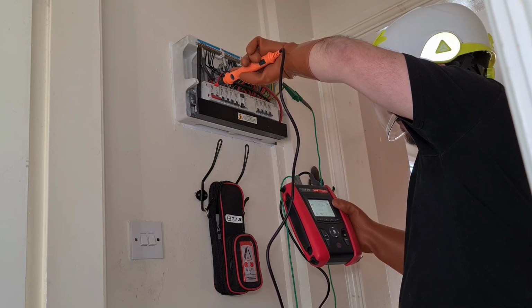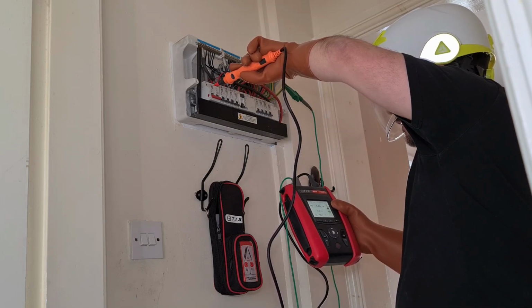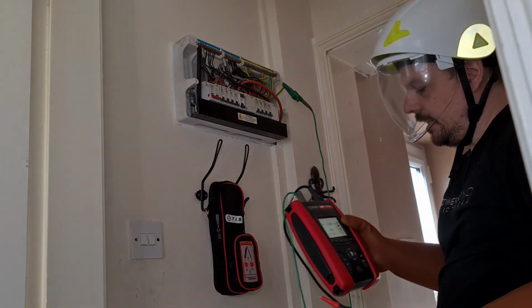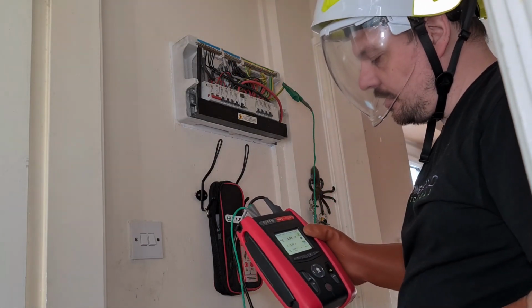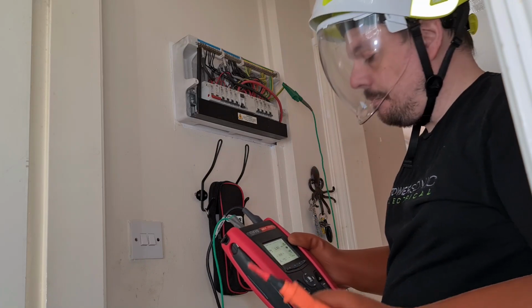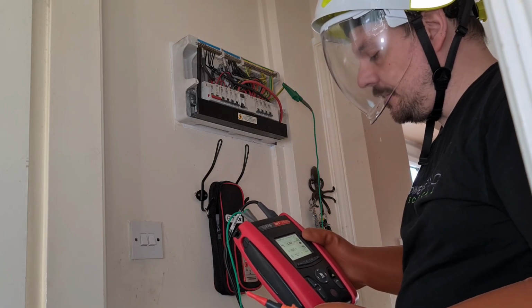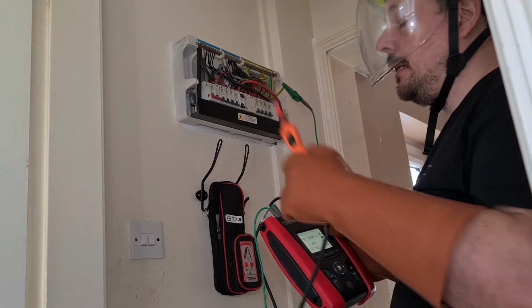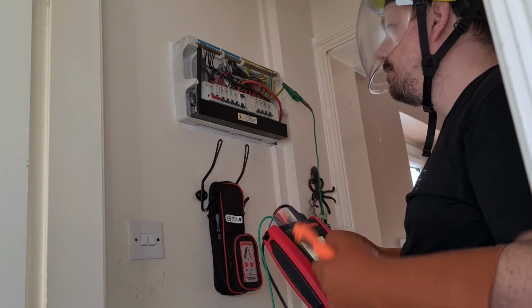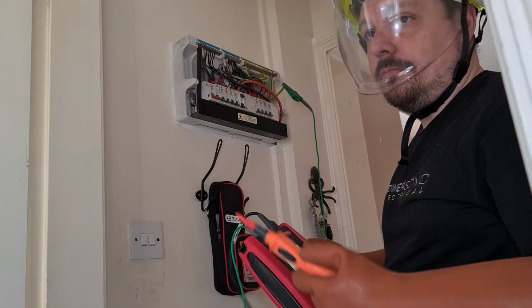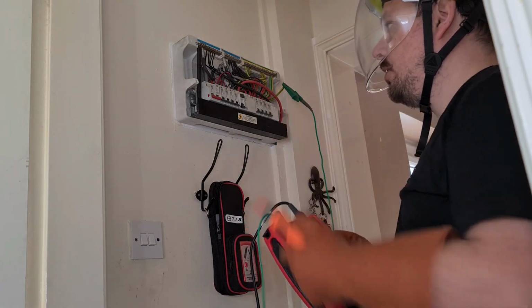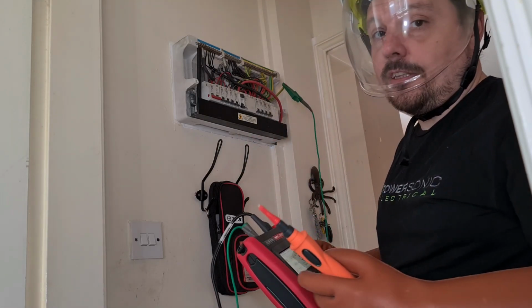I hit the go button on the probe and you can see I'm off there now. It's measured 0.17 and just over a kiloamp on the PFC as well. And obviously we now need to repeat that test between the line and neutral. So I'm going to go and get the long probe extenders on now. We'll do that on the main switch and see what value we get there as well.